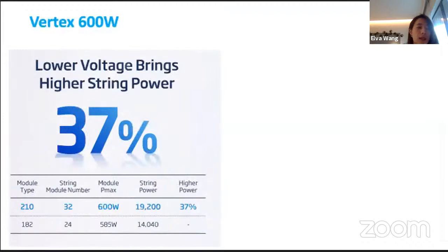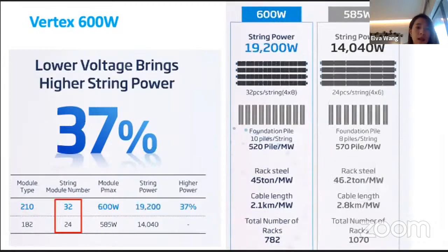For the 1,500 volt system, using 210mm cells, for the 600 watt module, one string can still connect 32 pieces, which is more than 19 kilowatts. For the 585 watt, 78-cell module, you can only connect 24 pieces, even less than the 72-cell 182, so one string only reaches 14 kilowatts. That means compared to 585, one string gives 37% more power.